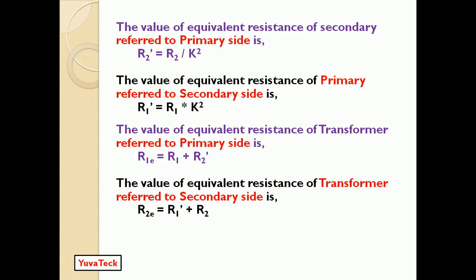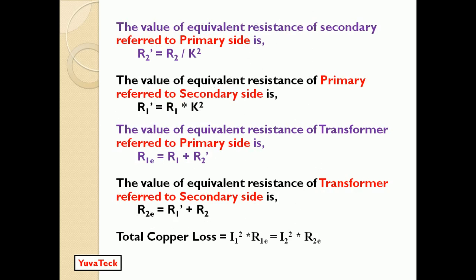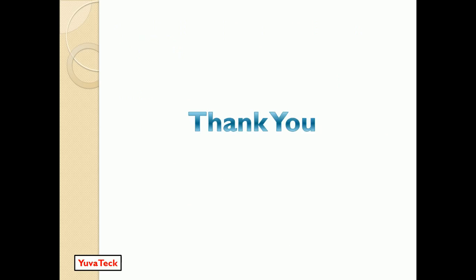The same kind of formula can be used to find out the reactance value as well as the impedance value — in place of R we can write X or Z. So these four formulas can be used to find out the equivalent values of reactance and impedances as well. You can verify the answer finally: if you substitute I1² × R1E as well as I2² × R2E, both will give the same value — that is, while calculating the total copper loss of the transformer, any one of these formulas can be used.